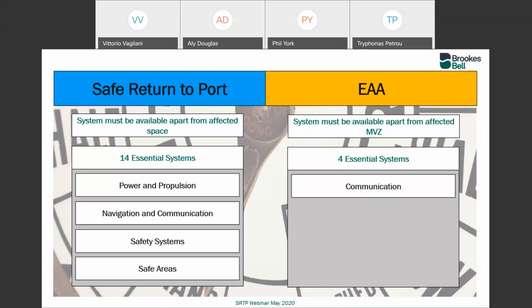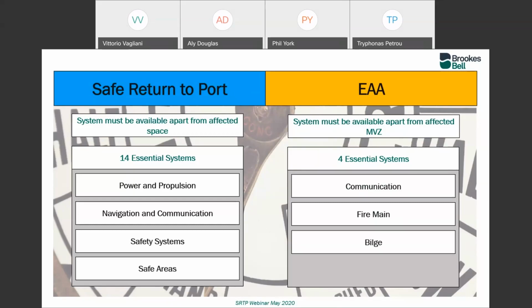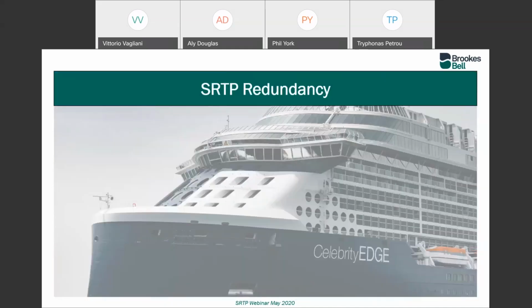In terms of evacuation and abandonment, it's obviously a smaller set of systems because we're only looking at the abandonment process. So we need the communication, again, both internal and external, the fire main to fight the fire that exists, the bilge system to remove the firefighting water, and obviously we need to make sure we've got the lighting and guidance systems to support a safe and efficient evacuation and abandonment process. So how do we achieve this?